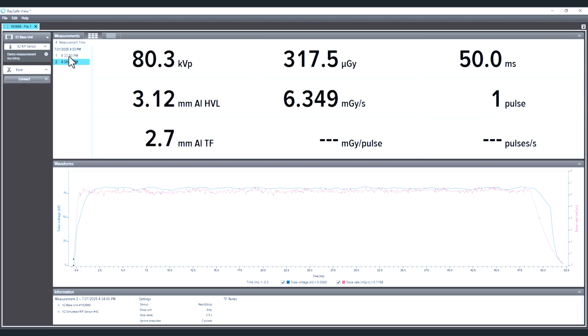The reason I like this view is because everything's in the same exact spot as on the base unit. All these cells are in the same order here as on the base unit. We have the KVP measurement, dose, exposure time, HVL, etc., all displayed the same way. We also now have the ability to see the waveforms. The blue waveform is the tube voltage or KV waveform, and the red is the dose rate or radiation waveform.